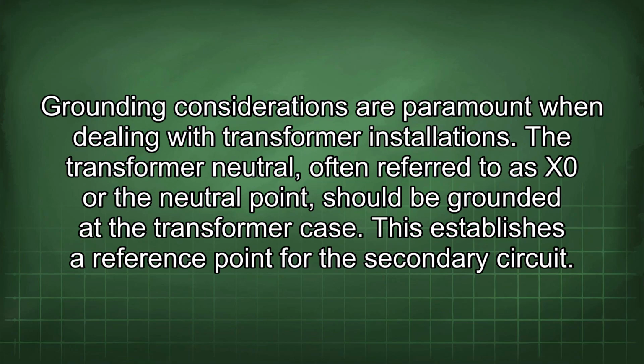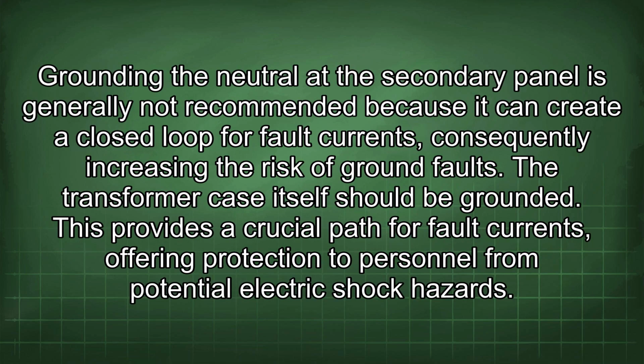Grounding considerations are paramount when dealing with transformer installations. The transformer neutral, often referred to as X0 or the neutral point, should be grounded at the transformer case. This establishes a reference point for the secondary circuit. Grounding the neutral at the secondary panel is generally not recommended because it can create a closed loop for fault currents, consequently increasing the risk of ground faults.